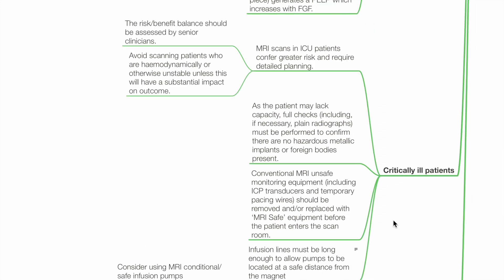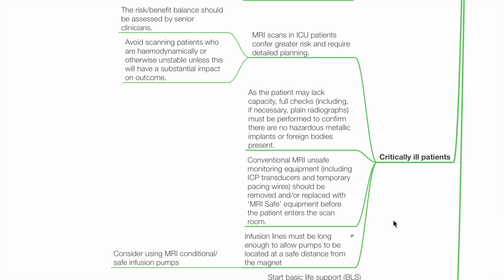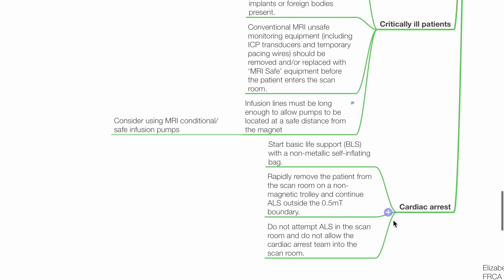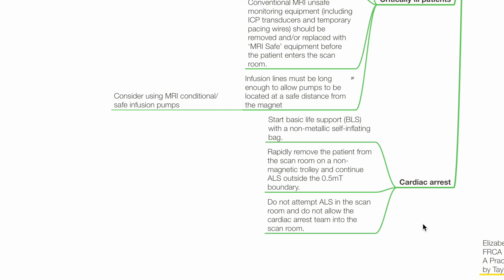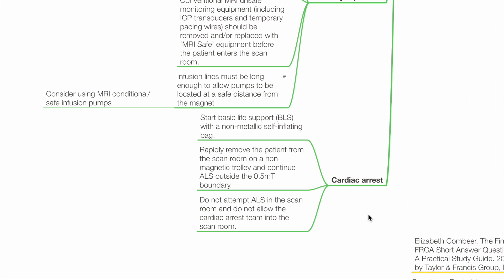Regarding critically ill patients: MRI scans in ICU patients confer greater risk and require detailed planning. The risk-benefit balance should be assessed by senior clinicians. Avoid scanning patients who are haemodynamically unstable unless there is substantial impact on outcome. As the patient may lack capacity, full checks must be performed to confirm there are no hazardous metallic implants or foreign bodies present. Conventional MRI-unsafe monitoring equipment such as ICP transducers and temporary pacing wires should be removed or replaced with MRI-safe equipment before the patient enters the scan room. Infusion lines must be long enough to allow pumps to be located at a safe distance from the magnet. Consider using MRI-conditional or MRI-safe infusion pumps.